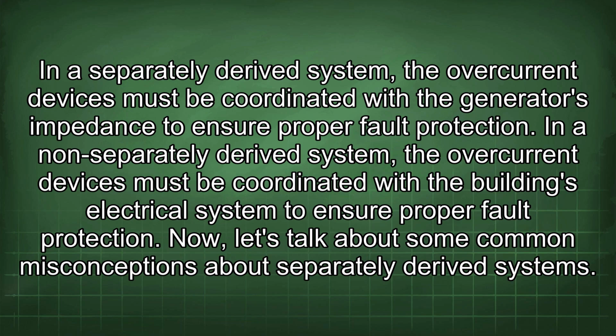In a separately derived system, the overcurrent devices must be coordinated with the generator's impedance to ensure proper fault protection. In a non-separately derived system, the overcurrent devices must be coordinated with the building's electrical system to ensure proper fault protection. Now, let's talk about some common misconceptions about separately derived systems.